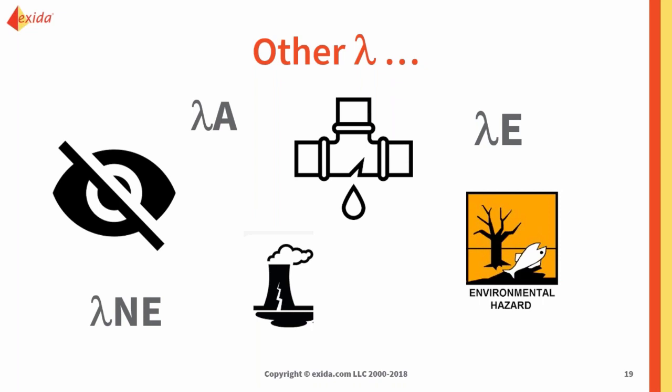So what does that mean? Remember those internal diagnostics that make something detected or undetected? This is a failure in those diagnostics or that system. So even though your SIF is going to still work and still do a demand correctly if a hazard occurs, you will not know in the future if a detected failure arises. So all of those dangerous detected and safe detected failures would then become dangerous undetected and safe undetected failures. Some examples of an annunciation failure could be your display is not showing up correctly or your internal diagnostics just not working.